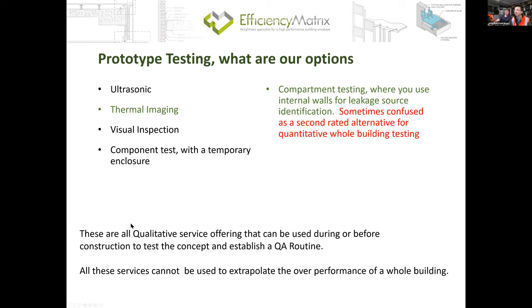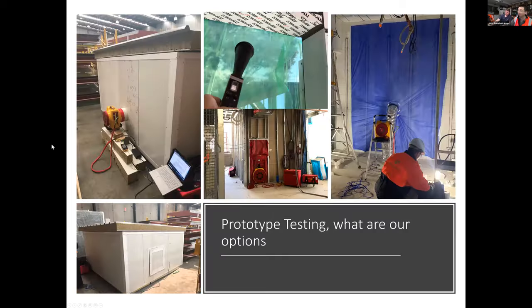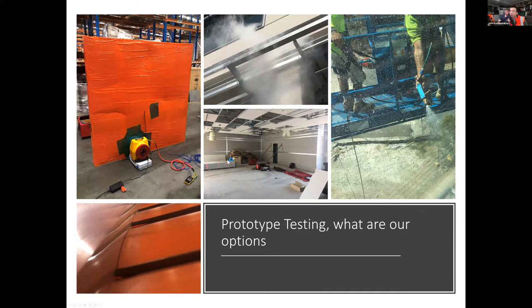Okay. Next, here are some examples of component testing. We can test a large smoke spill damper, and when we pressurize the damper, you can see some of the edges opening up slightly. When we do smoke testing or water testing, we can identify where the weak points are that smoke comes through. But if you are not using existing rooms or partitions to do that test, it can get quite expensive to create a temporary structure to enclose part of the facade.